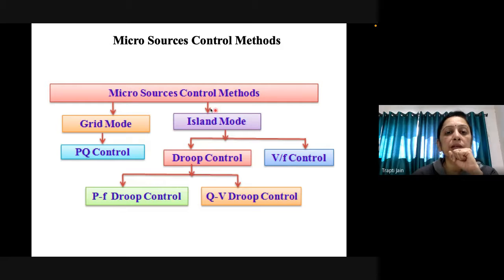The controller should be such that it automatically shifts from PQ control to droop control when islanding happens. It should shift to droop control if the disturbance is small, and automatically shift to V by F control if the disturbance is large.